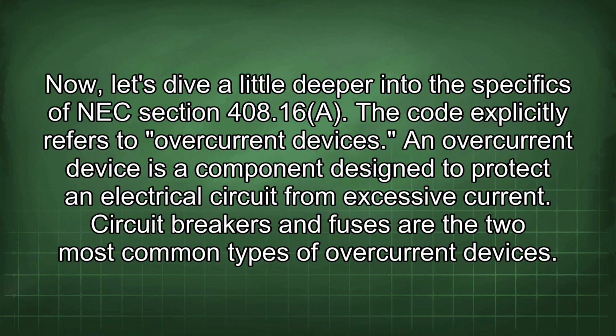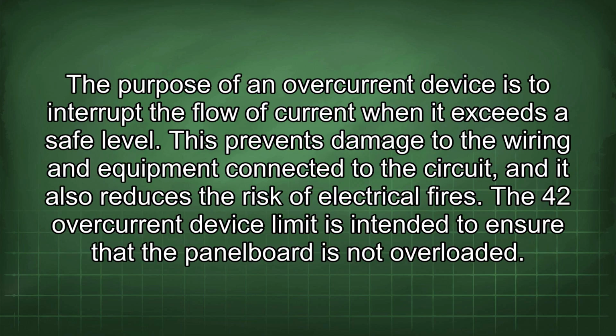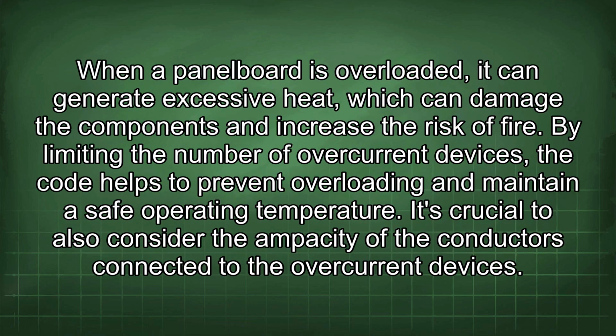Now let's dive a little deeper into the specifics of NEC section 408.16(A). The code explicitly refers to overcurrent devices. An overcurrent device is a component designed to protect an electrical circuit from excessive current. Circuit breakers and fuses are the two most common types of overcurrent devices. The purpose of an overcurrent device is to interrupt the flow of current when it exceeds a safe level. This prevents damage to the wiring and equipment connected to the circuit, and it also reduces the risk of electrical fires. The 42 overcurrent device limit is intended to ensure that the panel board is not overloaded. When a panel board is overloaded, it can generate excessive heat, which can damage the components and increase the risk of fire. By limiting the number of overcurrent devices, the code helps to prevent overloading and maintain a safe operating temperature.